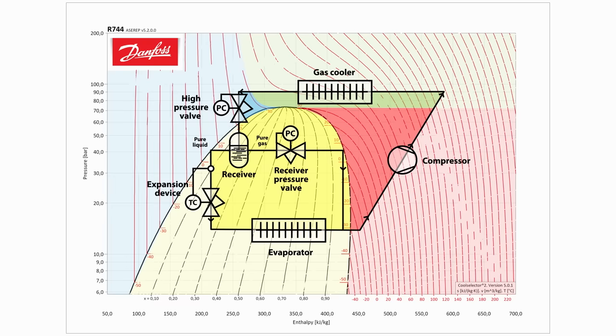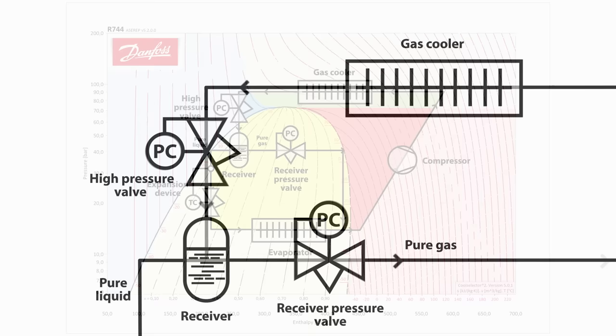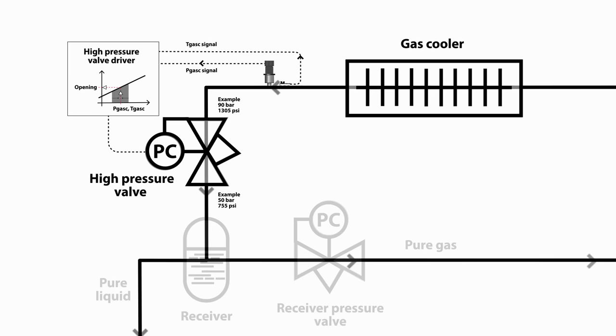But let's just have a closer look at the two pressure valves, starting with the high pressure valve. The opening degree of the HP valve is controlled by the outlets of the gas cooler, the temperature and the pressure.